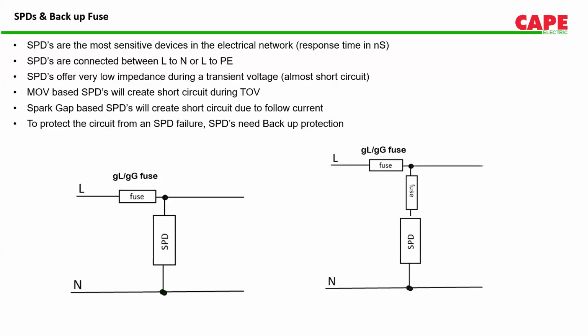Now, condition number two, when SPD fails in a short circuit mode, during that time there will be a short circuit current which flows through the SPD this way from line towards neutral or earth, whatever way the SPD is connected. Due to this short circuit current, the energy dissipated is quite high and the SPD can catch fire. So we need a backup fuse to ensure that the SPD is properly disconnected during the event of SPD failure.